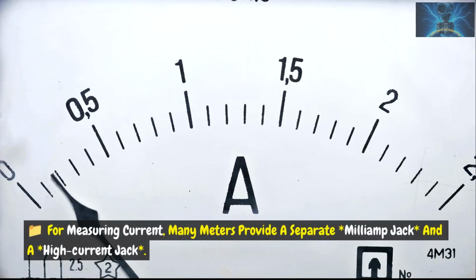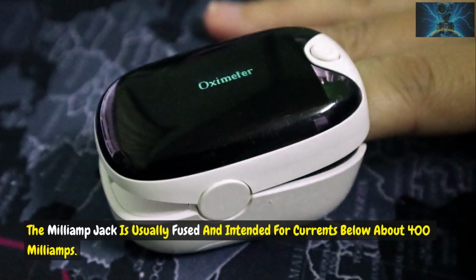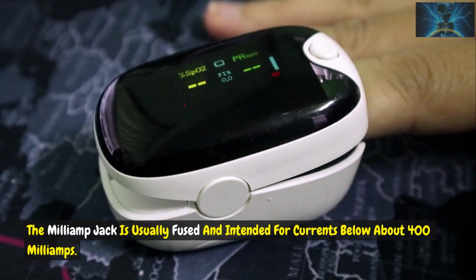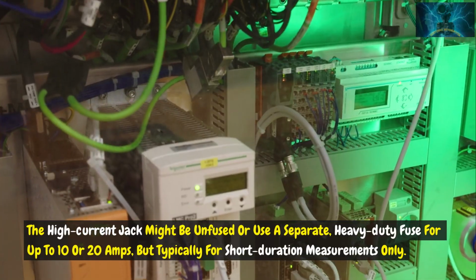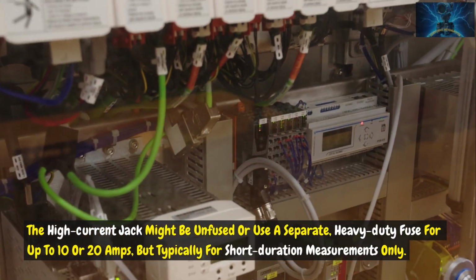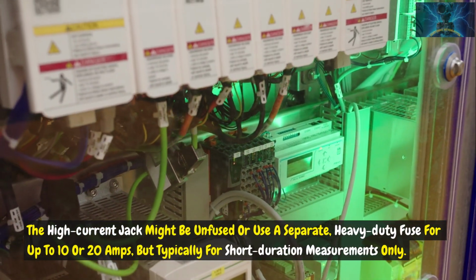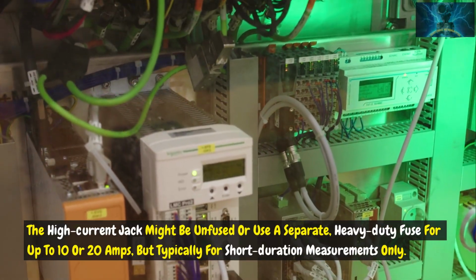For measuring current, many meters provide a separate milliamp jack and a high current jack. The milliamp jack is usually fused and intended for currents below about 400 milliamps. The high current jack might be unfused or use a separate heavy-duty fuse for up to 10 or 20 amps, but typically for short-duration measurements only.